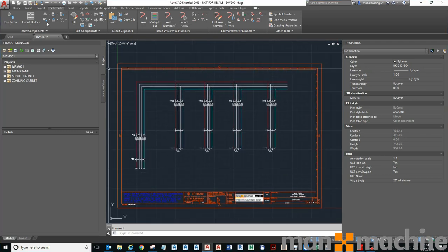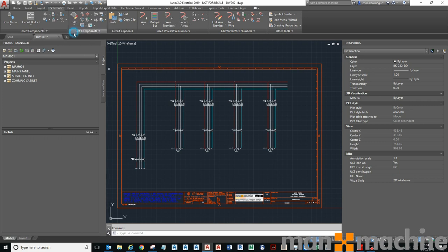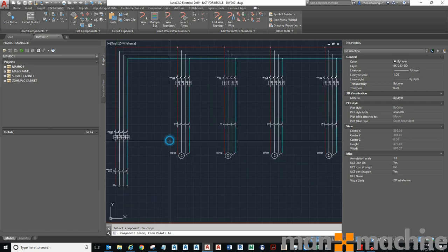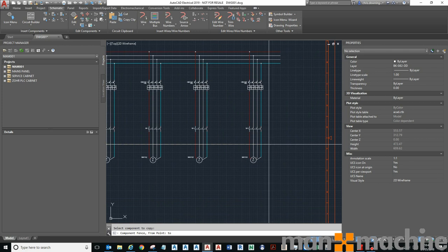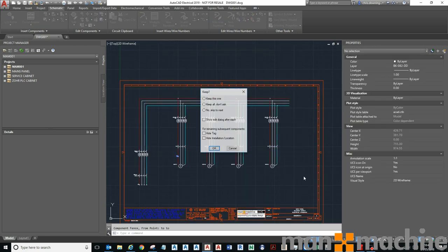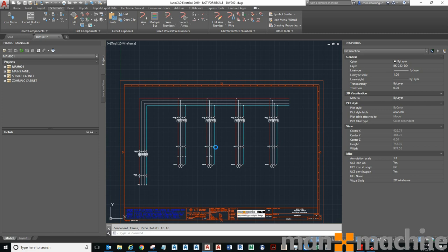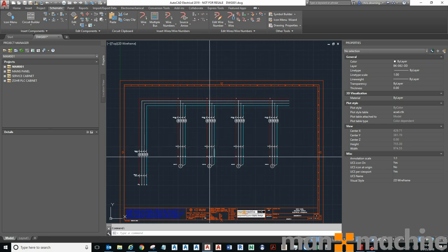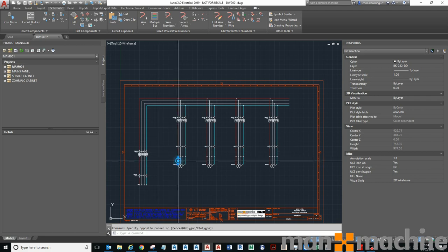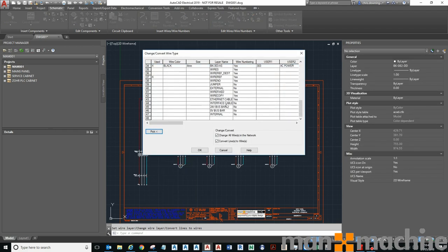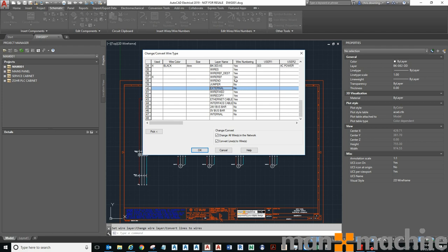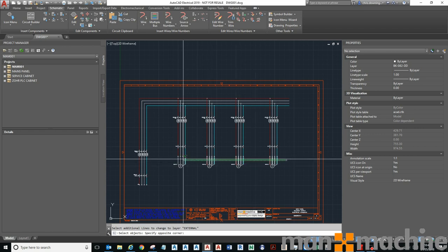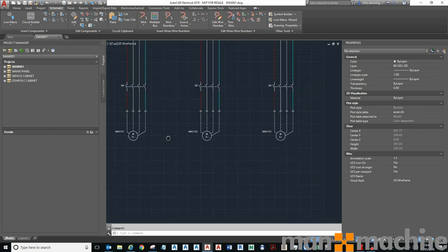Once I hide those description attributes, I can do the same but this time I'm going to pick from a master. These will be my terminals. Press enter, keep all, don't ask, don't show me in the dialog box. You'll see that it drops all my terminals on like so. I can change this wire type to an external wire type because it's external to the panel. You can see that I told it not to number anything that's an external wire.